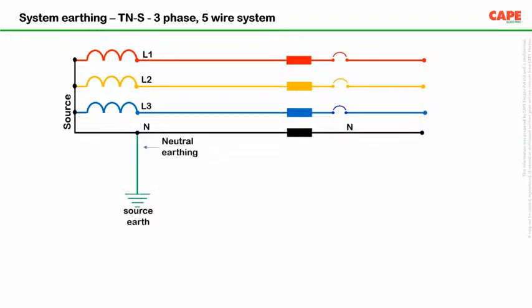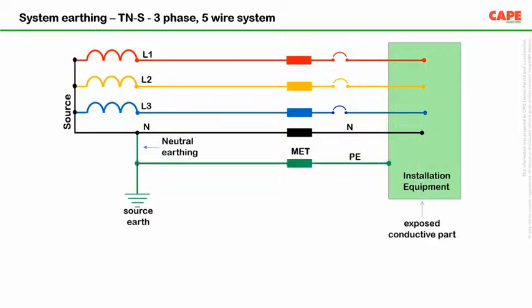You have the three phase, you have the neutral connected to earth, and now on the equipment side, the installation, that means maybe you have the main switchboard, the sub switchboard, a large distributed system with so many items. For the purpose of fault return, you are using a conductor. This is your earthing. The conductor is your earthing, not the earth pit.